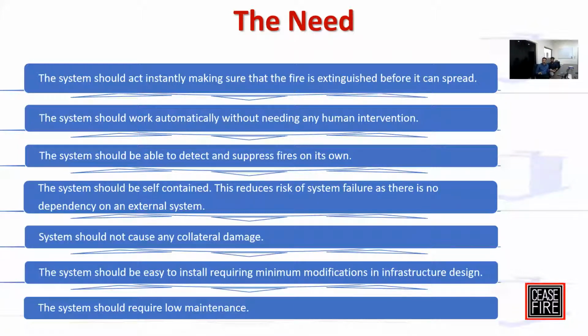It should be self-contained, with no electrical inputs required, because when generators catch fire, the first thing that happens is your power goes off. Any equipment dependent on that power will also shut down and won't be able to operate. So you need a complete mechanical system without any external interference.